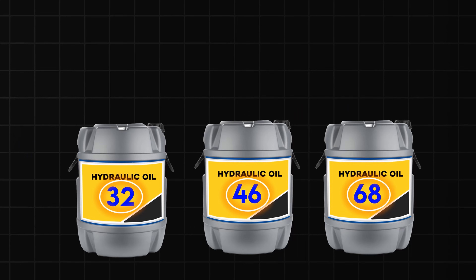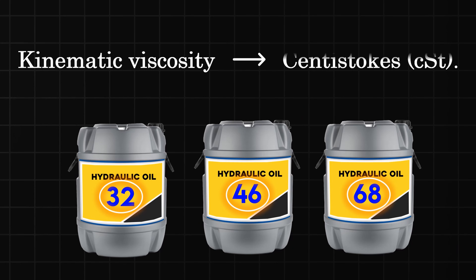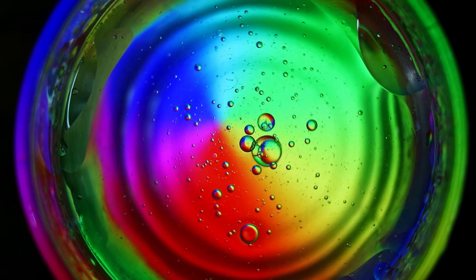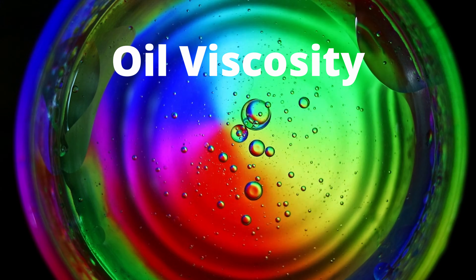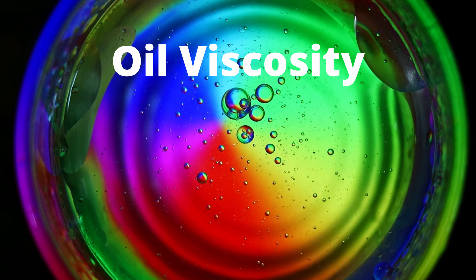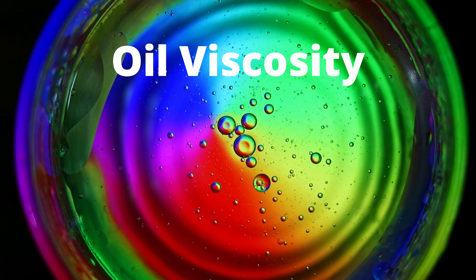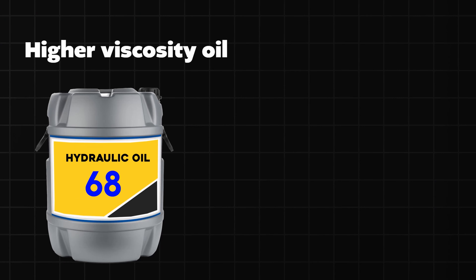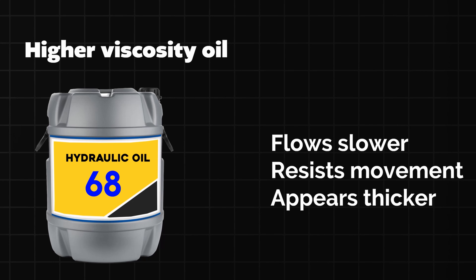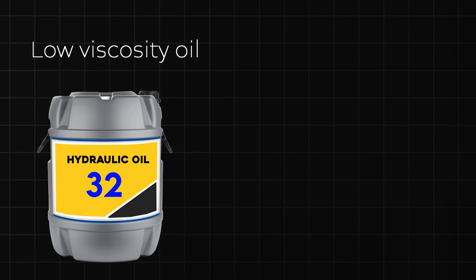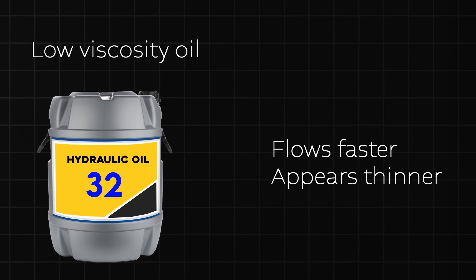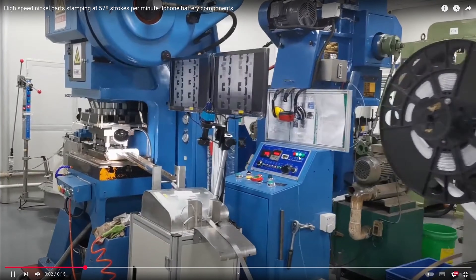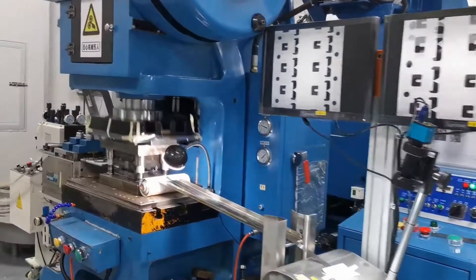These numbers represent the kinematic viscosity of oil in centistokes. Oil viscosity is a measure of how easily oil flows, or how much it resists flow. An oil with higher viscosity like oil 68 flows slower, resists movement, and appears thicker, whereas oil with lower viscosity like oil 32 flows easier, making it appear thinner. This is the one major factor in oil selection.